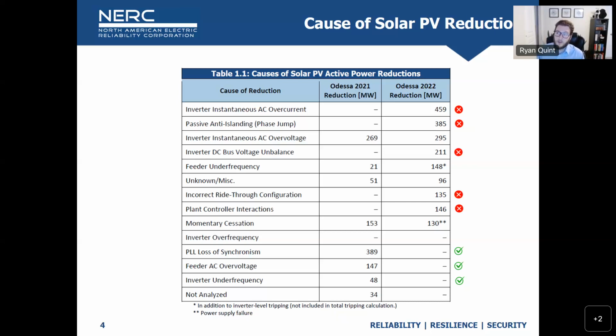In California, which has quite a bit of legacy DERs, when we have a fault, we see upwards of a couple hundred megawatts of DERs trip offline. Our speculation is those are legacy inverters, 1547 2004 or whatever compliant. In that environment, when the grid hiccups, they get off. 2018 really brought us a long way on the distribution side to have more robust devices down there. So it is helping, it has helped, but it doesn't help with regard to the stuff we talked about today.